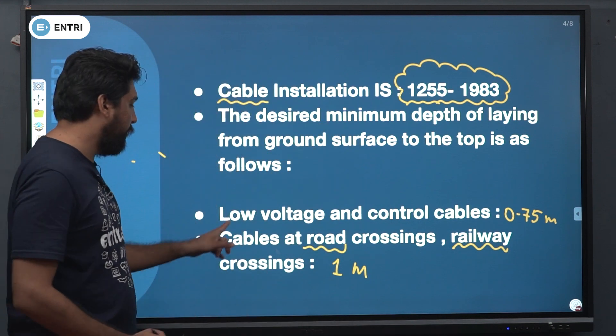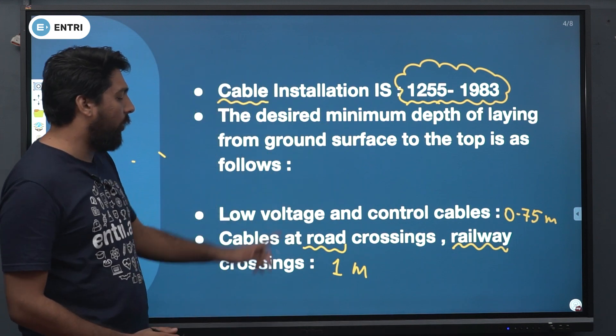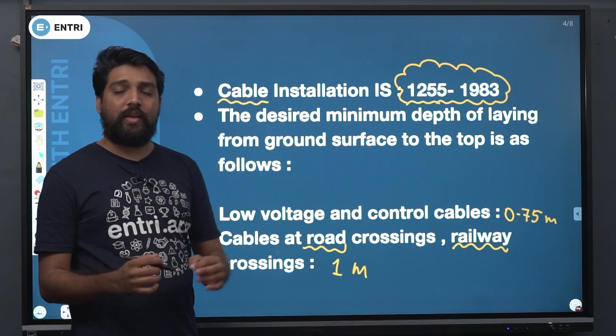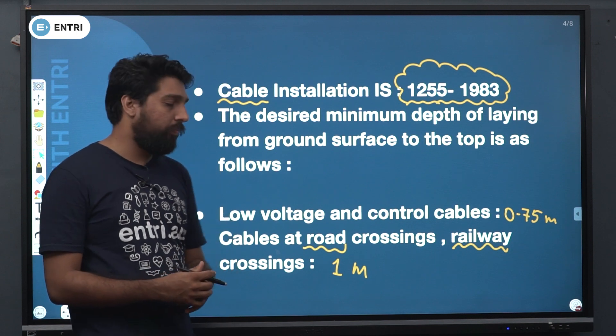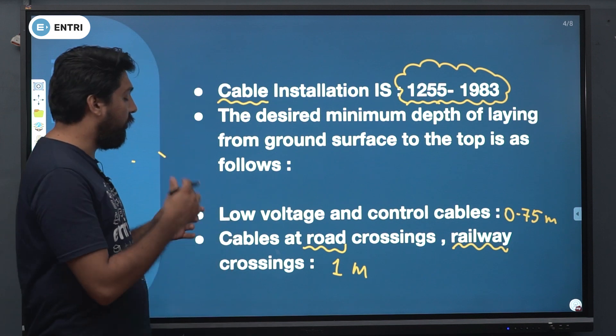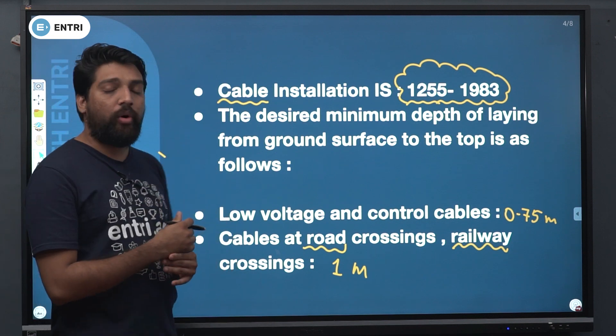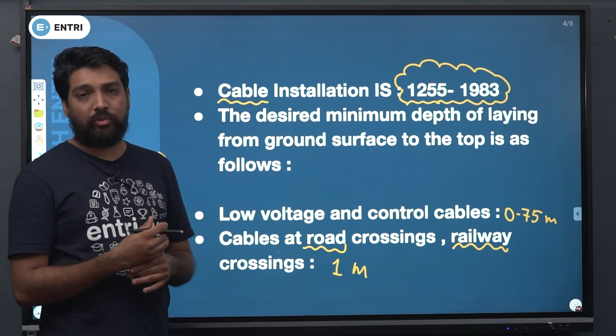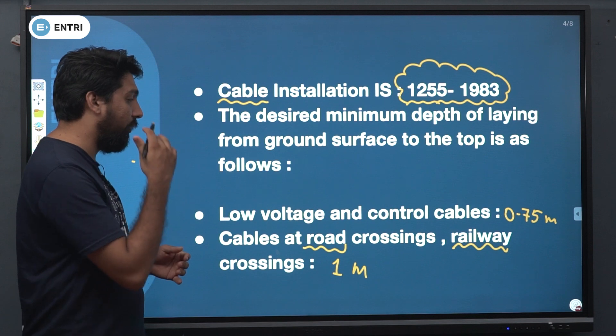So, both values: for low voltage and control cables, 0.75 meter. For voltage and control cables at road crossings, you have 1 meter.